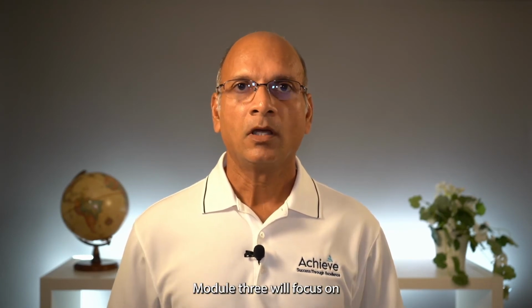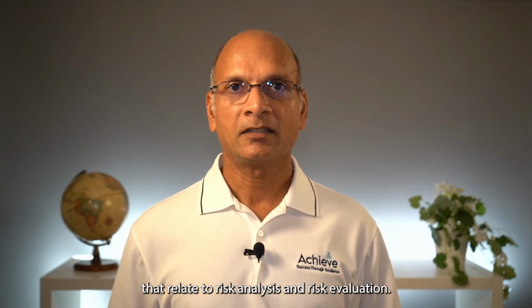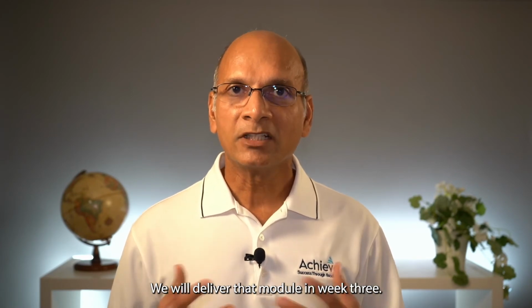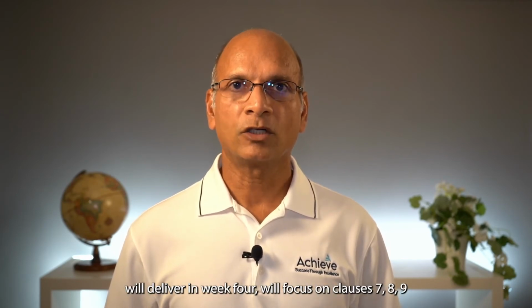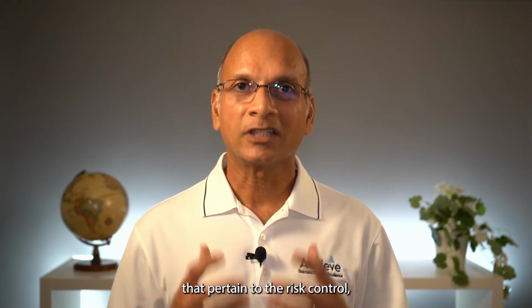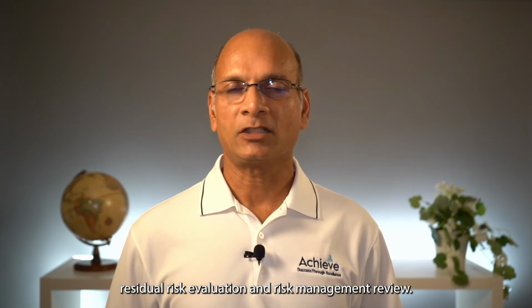Module 3 will focus on clauses 5 and 6 that relate to risk analysis and risk evaluation. We will deliver that module in week 3. Module 4, which we will deliver in week 4, will focus on clauses 7, 8, 9 that pertain to the risk control, residual risk evaluation, and risk management review.